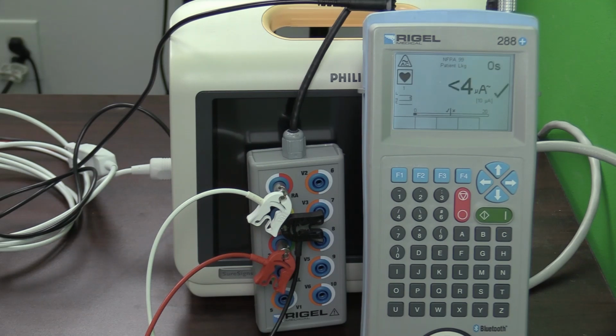Now you'll notice a few things about this. On the LCD screen, you have an AC warning. This is signaling to you that you should not touch any applied parts. These are live connections. And it is searching and receiving less than 4 microamps. And every time a check mark pops up, that is one lead passing a test. After it has cycled through all of the leads, the check mark will remain on the screen, signaling to you that the device has passed the test as a whole.